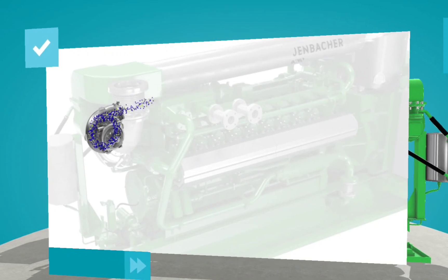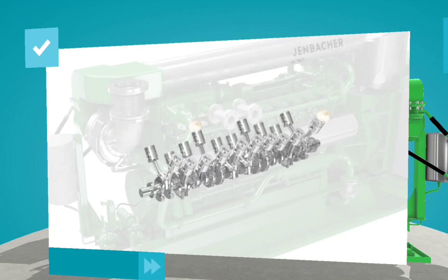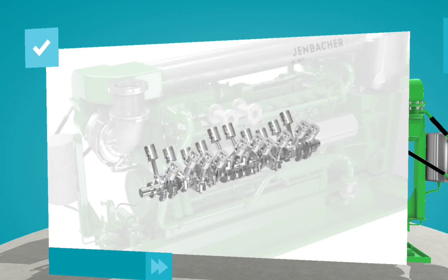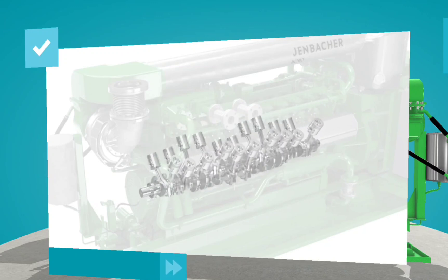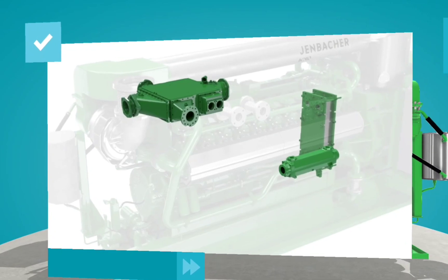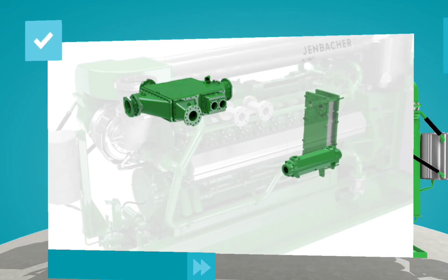Heat is produced when the air-gas mixture is compressed in the turbocharger, and then combusted in the combustion chamber. Heat exchangers around the engine extract heat directly from the air-gas mixture, from the oil circuit, and from the jacket water circuit.